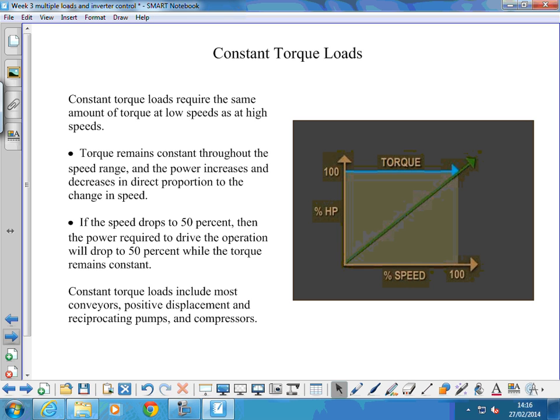If we look at constant torque loads, they require the same amount of torque at low speeds as at high speed. Torque remains constant through the speed range, and the power increases and decreases in direct proportion to the change in speed. So if the speed drops to 50%, then the power required to drive the operation will drop to 50%, meaning the torque remains constant. So again, we're putting less power in to get the same torque out because we're driving at a lower speed. Constant torque loads include most conveyors, positive displacement and reciprocating pumps, and compressors.